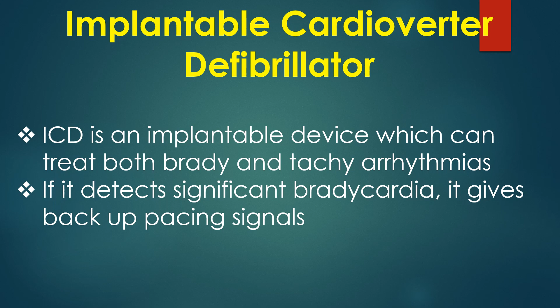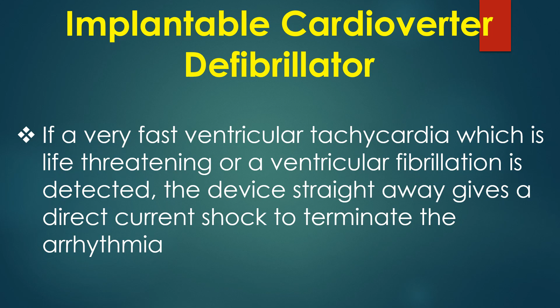If it does not succeed, a direct current internal shock is delivered across the high voltage coils to terminate the arrhythmia. If a very fast ventricular tachycardia which is life-threatening or ventricular fibrillation is detected, the device straightaway gives a direct current shock to terminate the arrhythmia. This is a single chamber ICD.